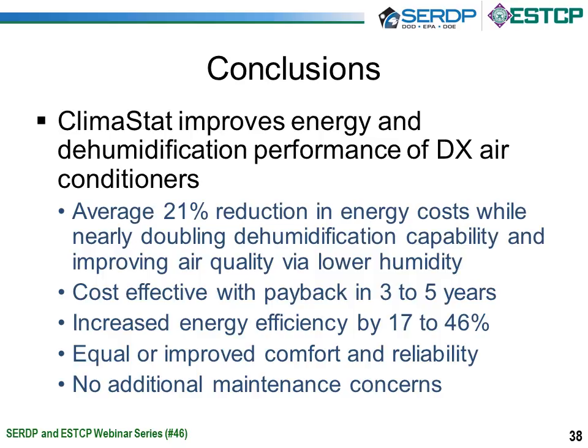In conclusion, the demonstration showed that ClimaStat improves the energy efficiency and the dehumidification performance of DX air conditioners. We saw on average 21% reduction in energy costs, doubling of dehumidification capacity, and improved air quality through lower humidity. Cost effective with payback from 3 to 5 years. The IEER ratings improved from 17 to 46%, depending on whether you're looking at the factory rating or the actual installed efficiency for the retrofitted units. Comfort and reliability was equal or improved, and there were no additional maintenance concerns.